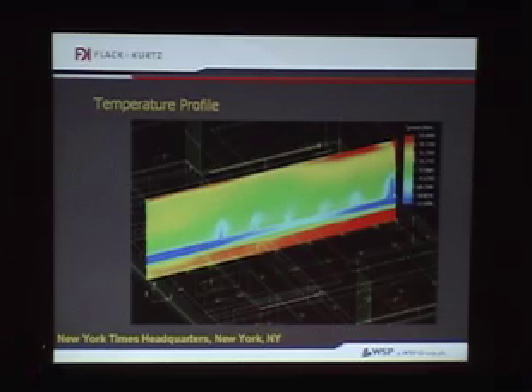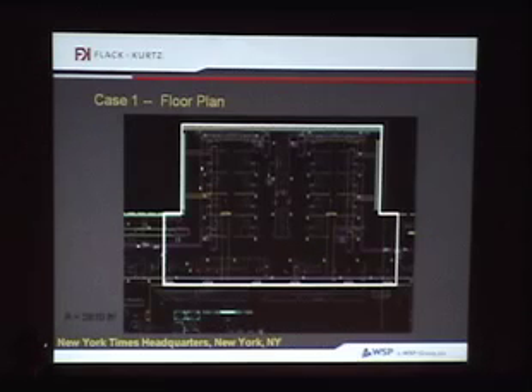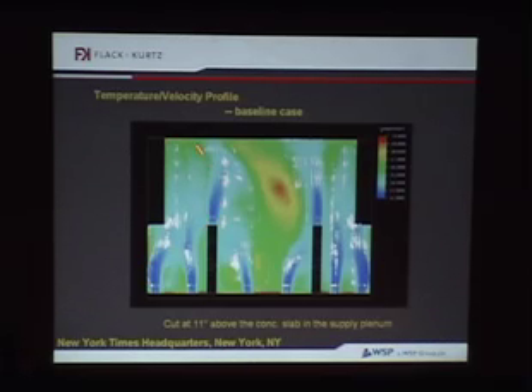One of the keys to a proper design, you notice that this is the ceiling plenum below, in red. The blue is the actual floor plenum of the cool air, and these are the air coming up out of the diffusers into the space, and again it gets hot up at the ceiling. The residence time of the air under the floor is what's really paramount in the design, to make sure that it doesn't take too long for the air to go into the floor, and once it gets into the floor, to get out into the space. We also modeled that floor plan to make sure that was not going to be the case. And while intuitively we believed we needed these little extensions from this core loop to help the air get out to this remote perimeter, what we actually found is that by jetting the air out there, we created currents under the floor. And the air actually circles and circles and circles before it loses that velocity and comes out of the diffuser.